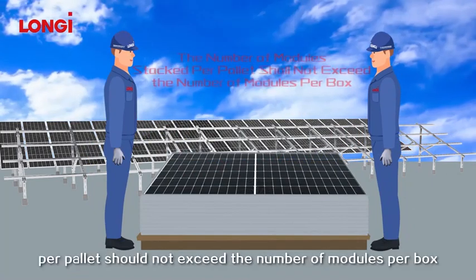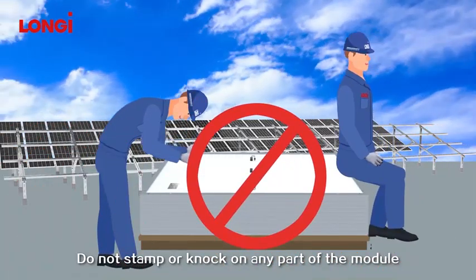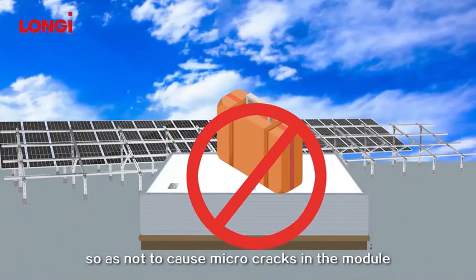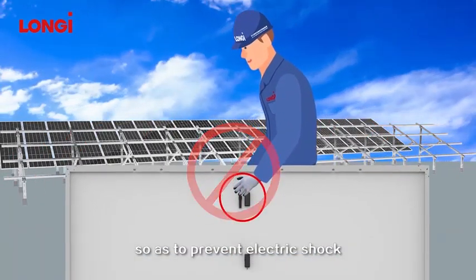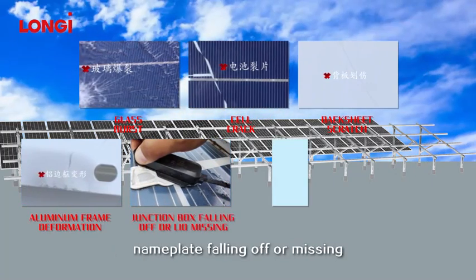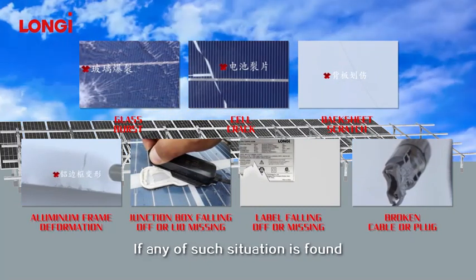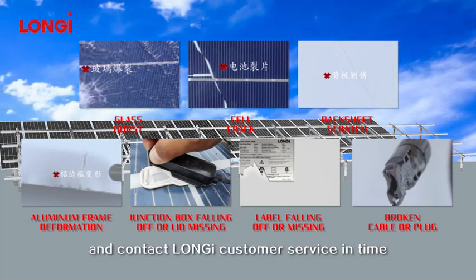The number of stacked modules per pallet should not exceed the number of modules per box. Do not stamp or knock on any part of the module. Do not stand or put heavy objects on the module so as not to cause micro-cracks. Do not touch the junction box or the metal connecting the cable to prevent electric shock. Carefully check the module before installation for glass burst, cell fragment, back sheet scratch, aluminum frame deformation, junction box falling off or lid missing, nameplate falling off or missing, broken cable or plug, and other anomalies. If any such situation is found, please record it by taking pictures, file it, and contact LONGi customer service in time.